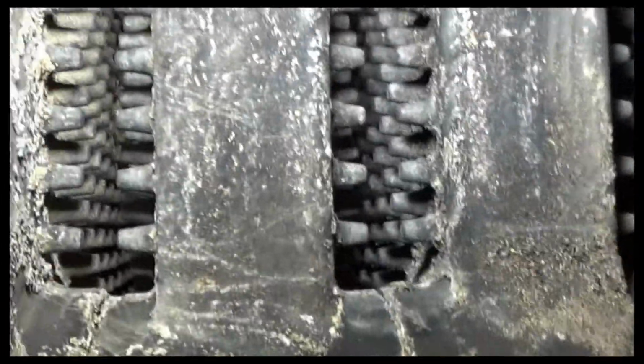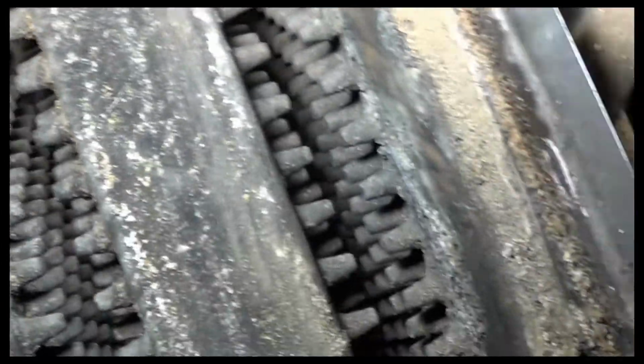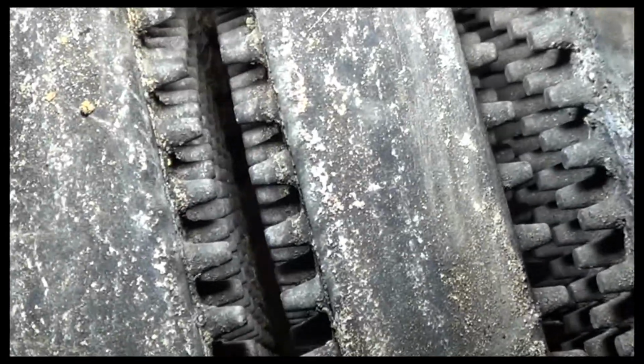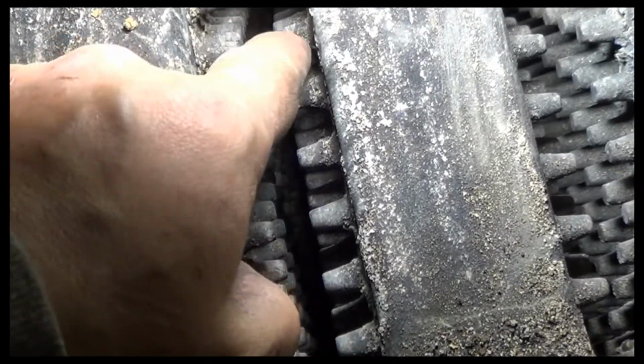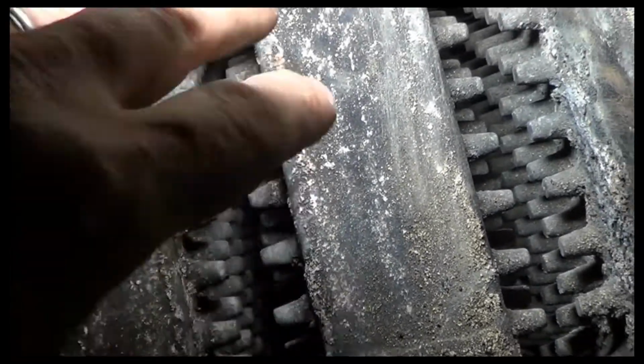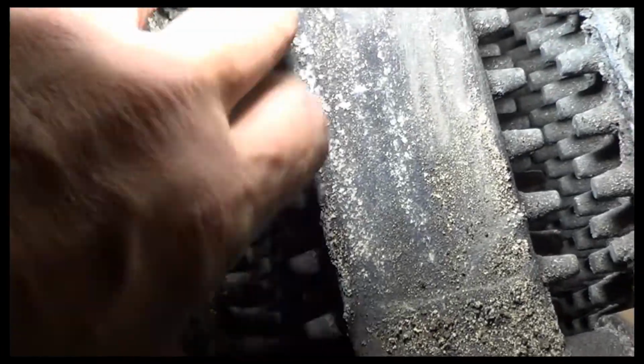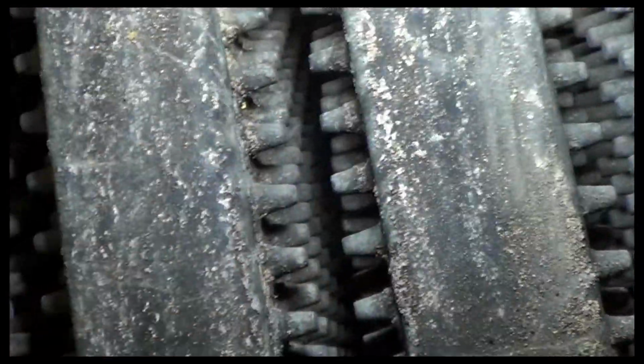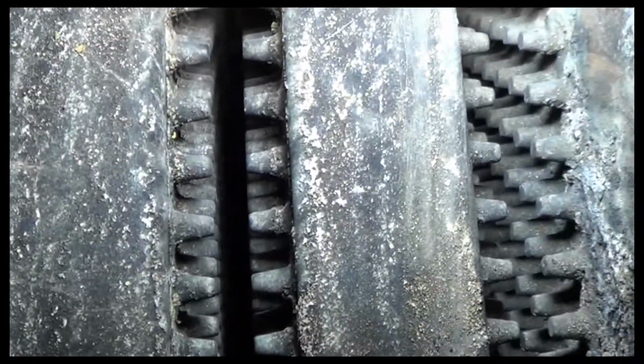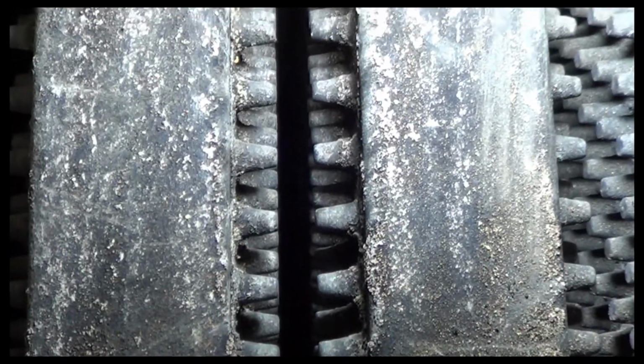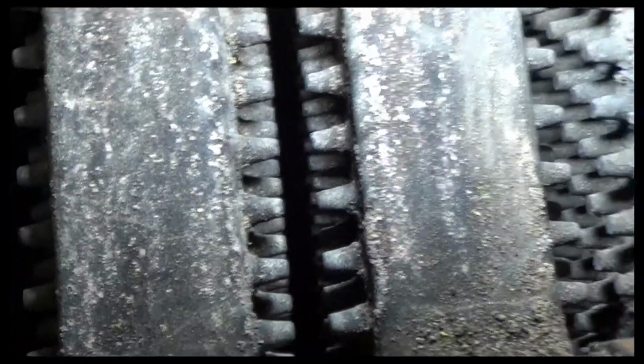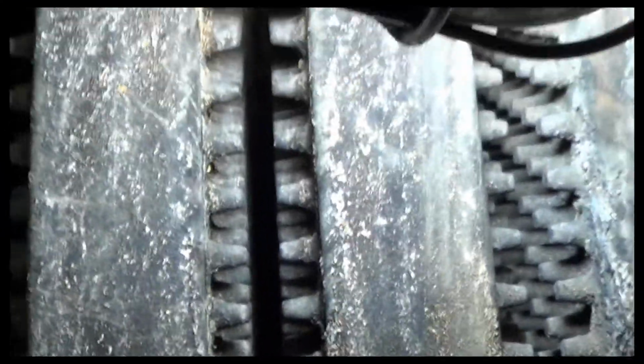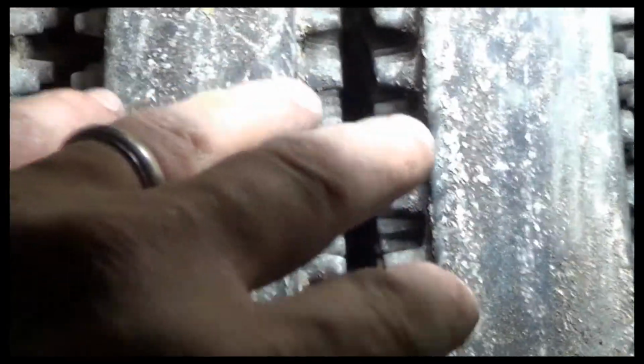We're back. You can see she's clean. All the nooks and crannies are done. You can see down through the heat exchanger. If you don't clean these, what happens is these pins, they soot up side to side and you get no heat transfer. You lose all your efficiency. And if you don't stay on top of it, eventually this turns into one big solid block of carbon. So hard you cannot get through it and your boiler is done, kaput, and junk. So you have to stay on top of these pin design boilers. This is ancient technology. They still do it.